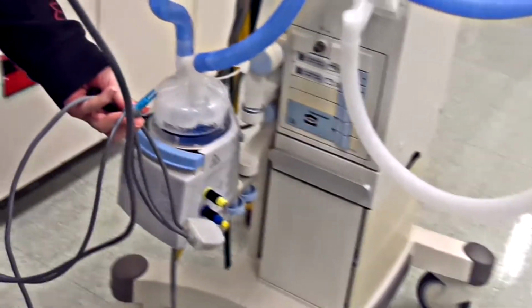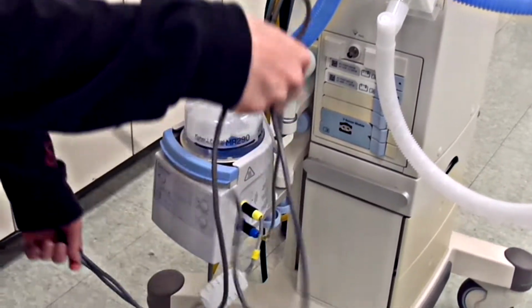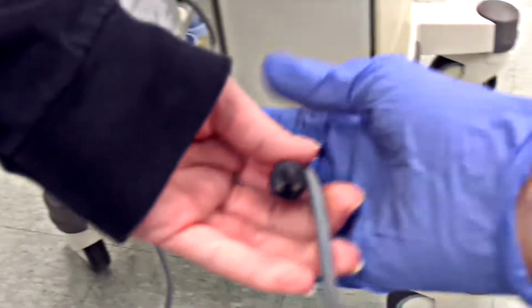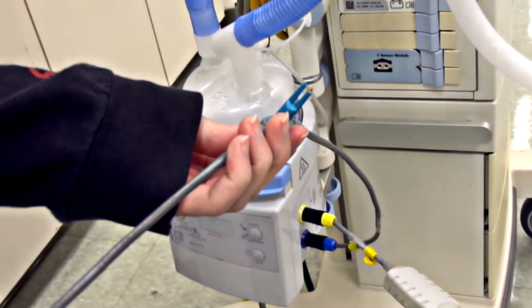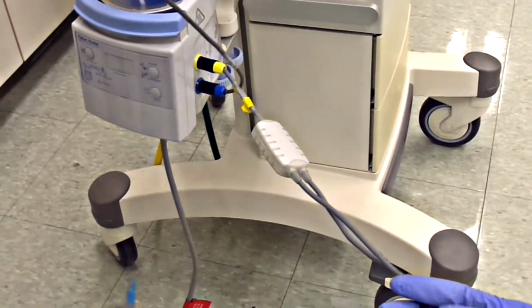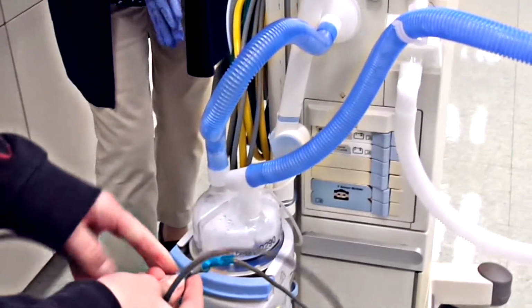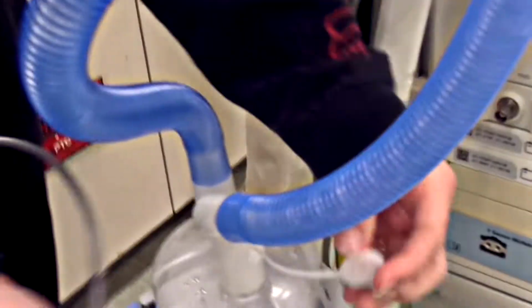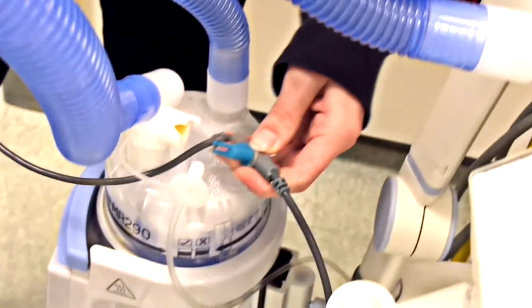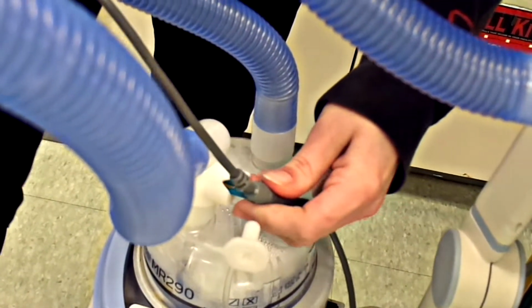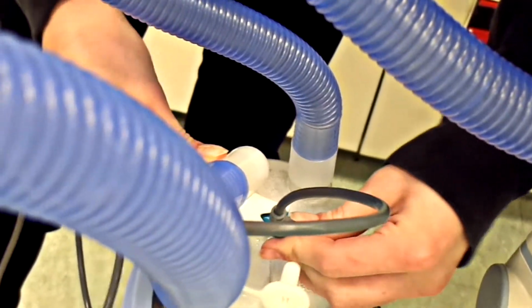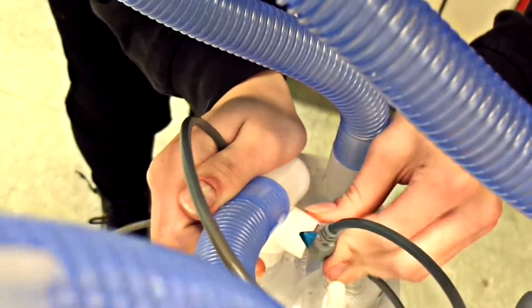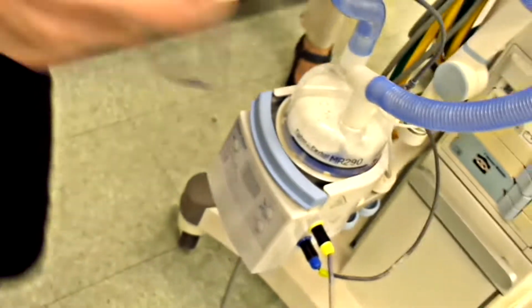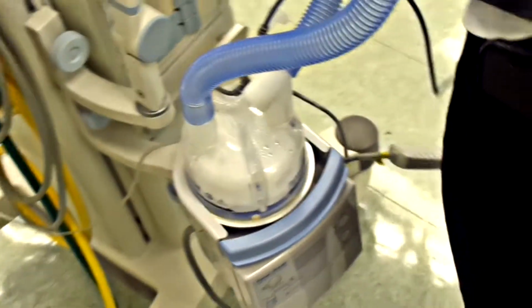Bottom connection blue is for the temperature cable. You will notice that the cable has two sensors. Plug the sensors into the proper ports. One sensor is plugged into the circuit, where the circuit attaches to the water chamber. It sends information back to the humidifier about the temperature and flow at that point in the circuit. The longest end connects into the port at the patient Y. Make sure it is on the inspiratory side. This sensor senses the temperature of the inspiratory gas right before it enters the lungs. If the temperature reads below 39 degrees Celsius, the heater wires will turn on. If the temperature is above 39 degrees Celsius, the heater wires will turn off.